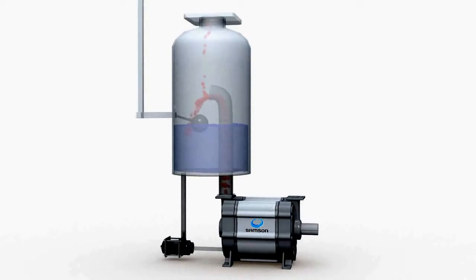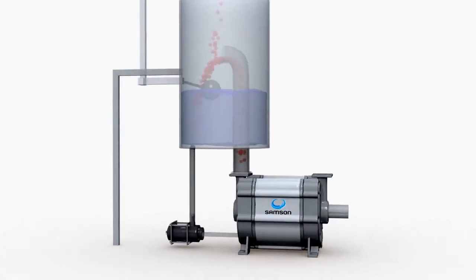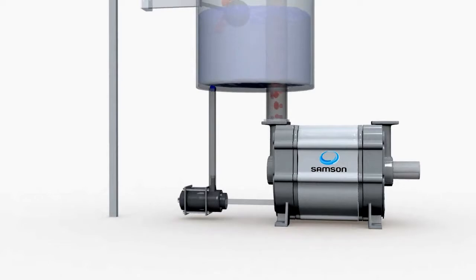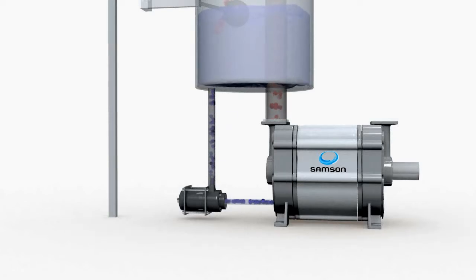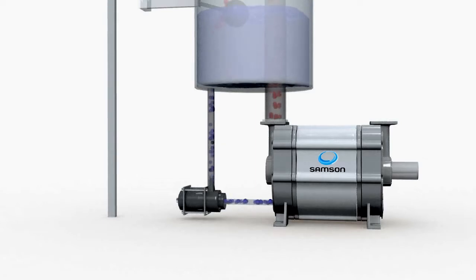To ensure the correct liquid level in the pump, the system is fitted with a service liquid valve. When the service liquid valve is connected to the water supply, it will replace any evaporated liquid. As the liquid level is above the level of the pump, the supply of liquid to the pump should be shut off when it is not running. We have therefore developed a special valve specifically for this purpose. The service liquid valve is opened by pilot pressure created by the liquid ring in the pump. There is thus no need for an external control. This valve is listed in our product range under Valves.